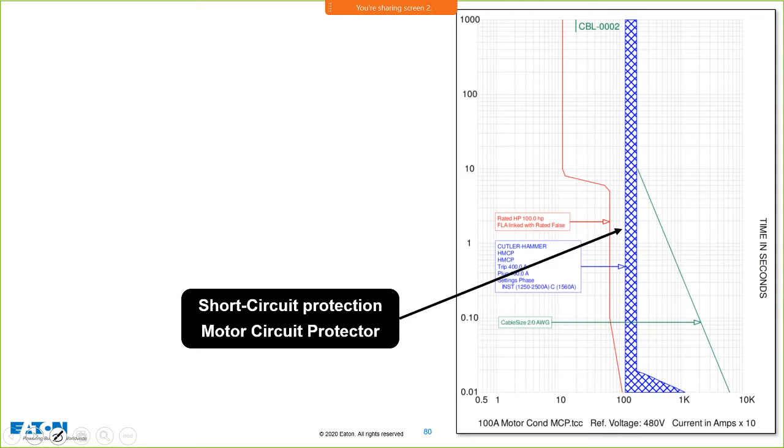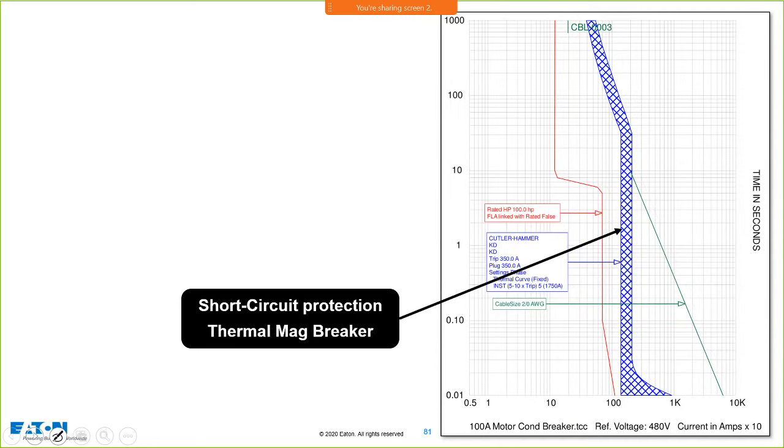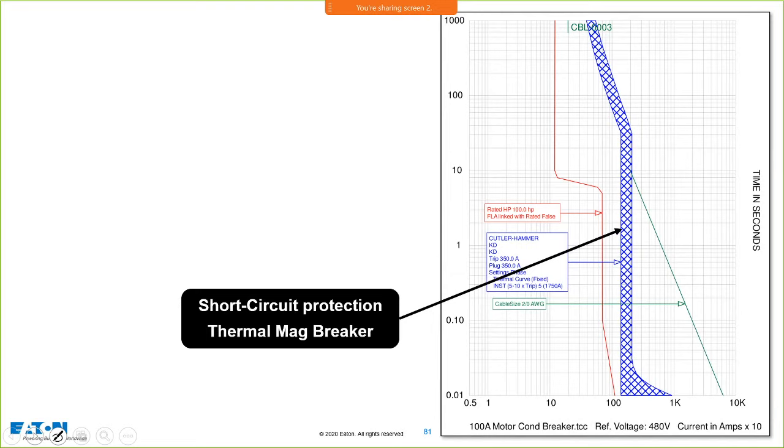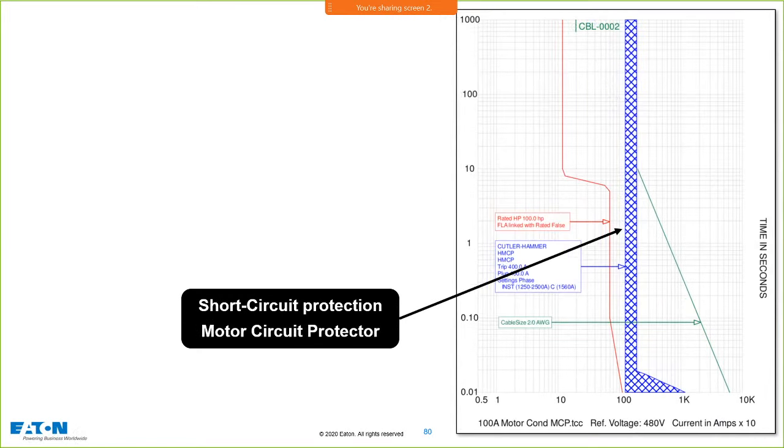So that's basically what that looks like for short circuit protection only. And it can be adjustable. I can move that in different, this one here is, that's a 350 that you'll notice. Let me just go between the two. If you look down at the bottom right here, having troubles with my touchpad. So if you look right down here, the separation in between where that cants over, for this one, which is programmed to go at 1560 instantaneous, this one's 1750. So you can adjust that instantaneous and move it higher.